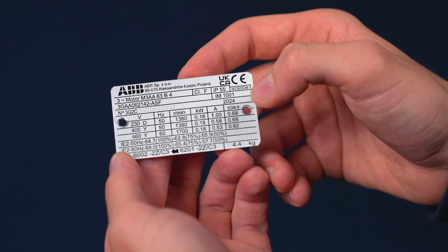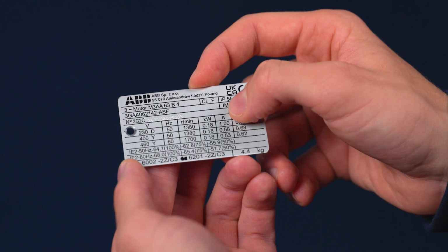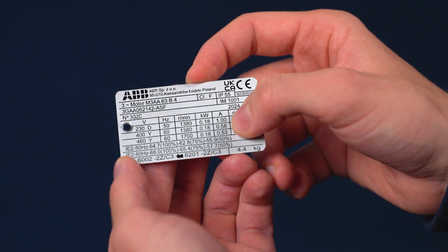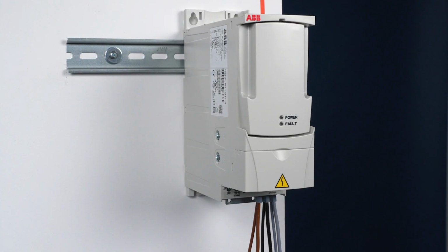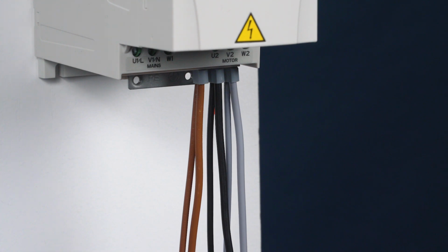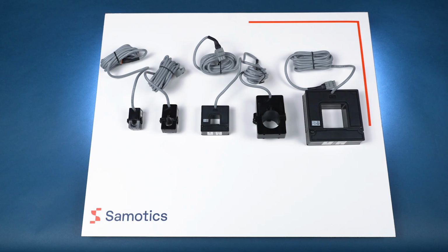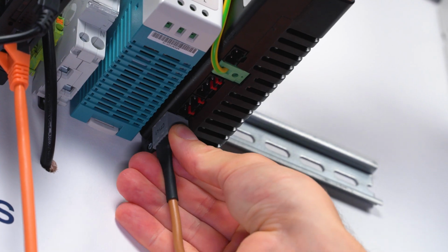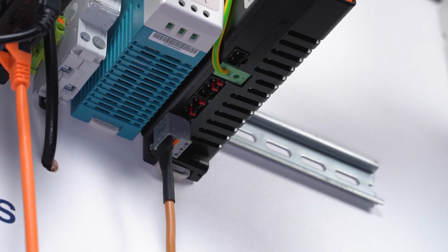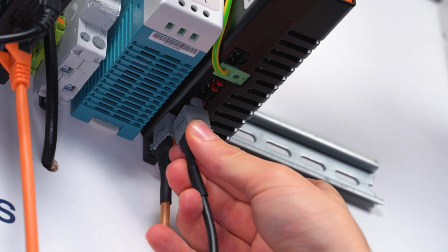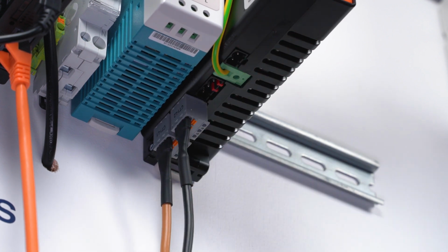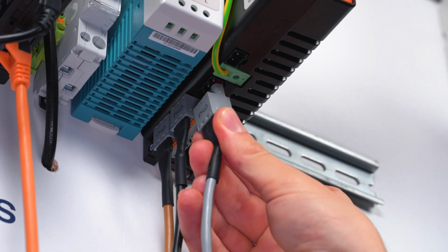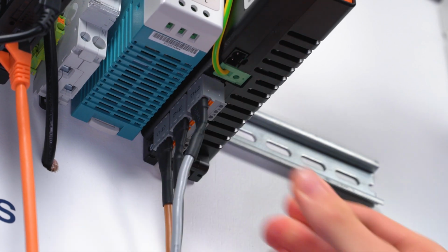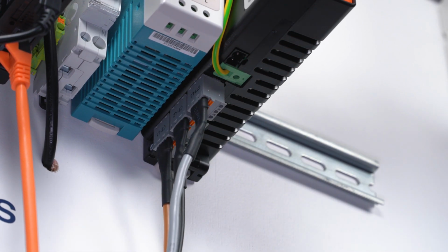Set up current measurements by first checking that the motor amperage is within the current transformer's rated range. For motors with multiple wires per phase, divide the motor current by the number of wires and ensure the current transformer's rating matches. Plug the current transformer's connectors into the NOVAQ ports in the following order: Phase 1, brown, to the port closest to the DIN rail, Phase 2, black, to the middle port, and Phase 3, gray, to the port furthest from the DIN rail.